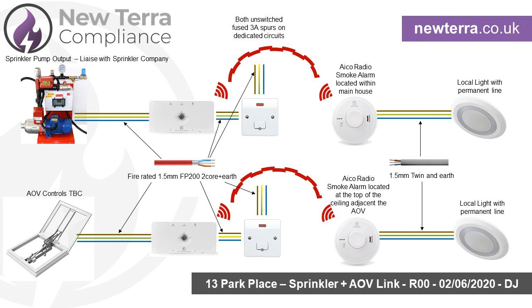So to meet the fire engineering's recommendations, they had to link the smoke alarm system with the sprinkler system and the AOV with the fire alarm system. The idea being, when a fire is detected, it opens up the AOV to allow smoke out, and also that when the sprinkler system activates because there's a fire, there's an audible alarm. So this is just something that I've produced.